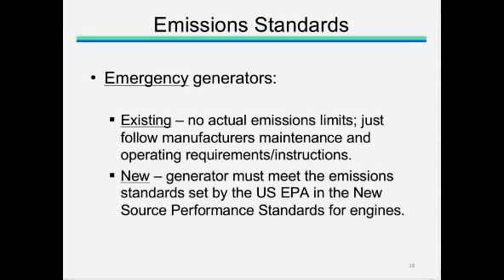Under the model rule, an existing emergency generator does not have a specific numerical emission standard with which to comply, but they must follow manufacturer's maintenance and operating requirements to help minimize emissions. Alternatively, a new emergency generator must meet the applicable emission standards set by the US EPA and the new source performance standards for either compression ignition or spark-ignited engines.